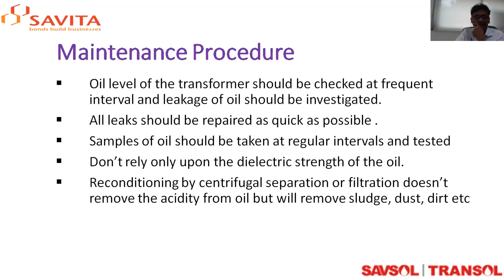Apart from this maintenance procedure, one has to look into what type of filters you are using. You are using clean filters. There is a Fuller's treatment. One can go for the Fuller's treatment to reduce the acidity, because once acidity is formed in the transformer, it is going to increase. So one has to look into the commercial aspect of that, and accordingly take the decision whether to go for the Fuller's treatment or not.